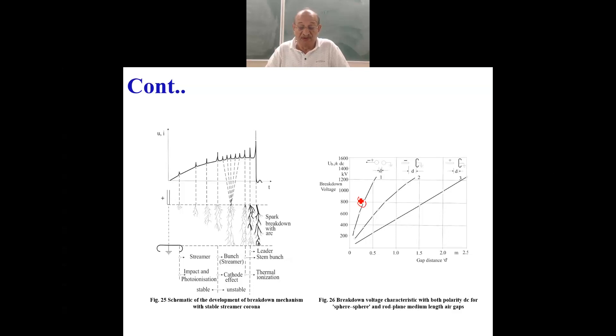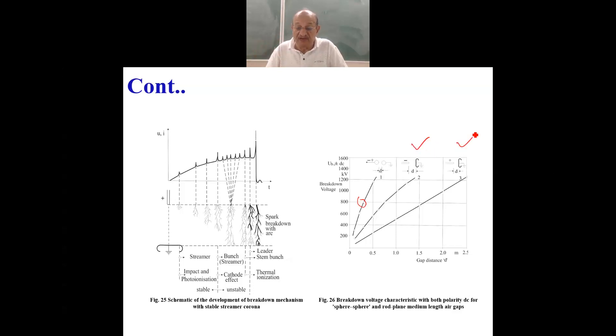Now we go to the other type of electrode, that is rod and plane. When we have a gap distance of even maybe 5-10 centimeters, it may be weakly non-uniform field. But when we increase the gap distance, the field becomes extremely non-uniform. Under both these conditions - small and large gap with rod and plane - the field is extremely non-uniform, and stable partial breakdown activity precedes the global breakdown.